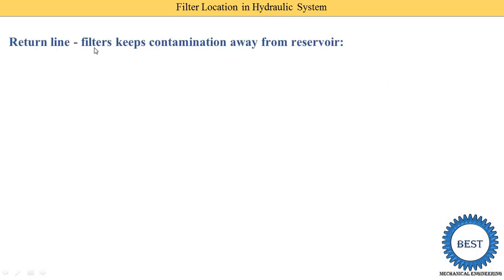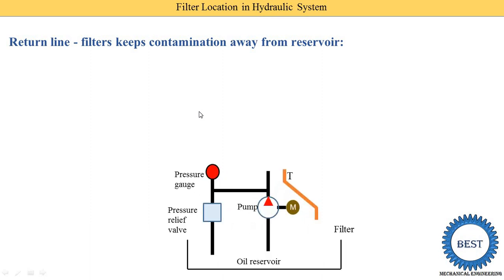The third location is the return line filter. Return line means the oil supplied from the pump goes through the directional control valve and actuators, and when the oil returns from the actuators through the directional control valve, a filter is provided on that return line. The return line filter keeps contamination away from the reservoir. It is considered the best option because contamination is removed at the outlet of the system before the oil re-enters the reservoir.